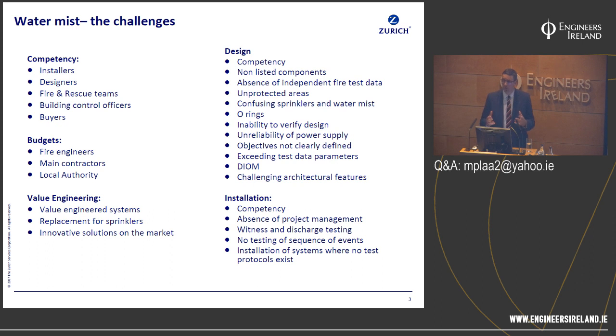But for example, one simple example is it may not cover 100% of the building. So quite clearly the water mist system is going to be cheaper than the conventional sprinkler system if we're not covering all areas of the building. And I'll give you a good case study where that's highlighted. And budgets have been a big driver also for water mist. Water mist being promoted as an alternative to sprinklers. And as I said, it can be a good solution in many applications.